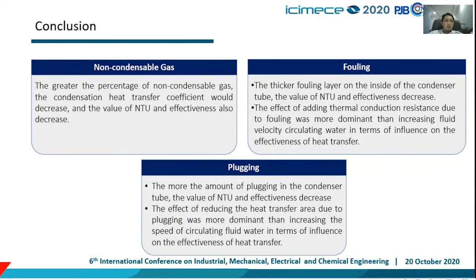The conclusions of this paper are as follows. The greater the percentage of non-condensable gas, the lower the condensation heat transfer coefficient, and the values of NTU and effectiveness also decrease. The thicker the fouling layer on the inside of the condenser tube, the lower the NTU and effectiveness values. The effect of added thermal conduction resistance due to fouling was more dominant than the increase in circulating water velocity in terms of influence on heat transfer effectiveness.